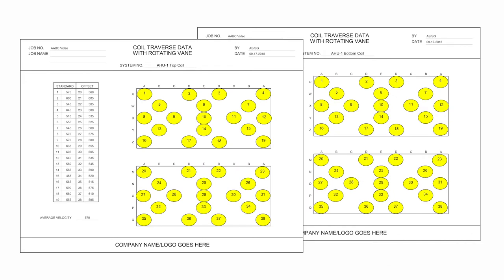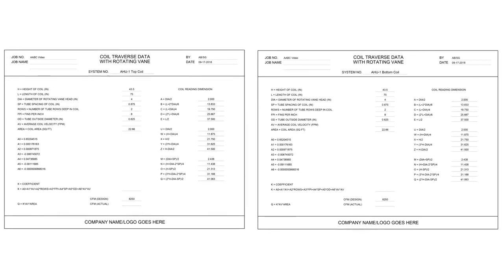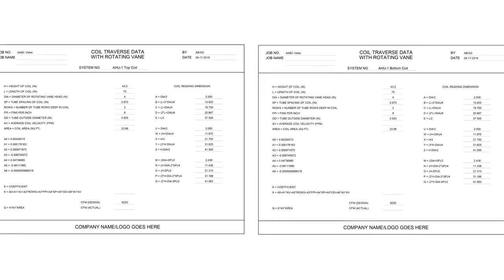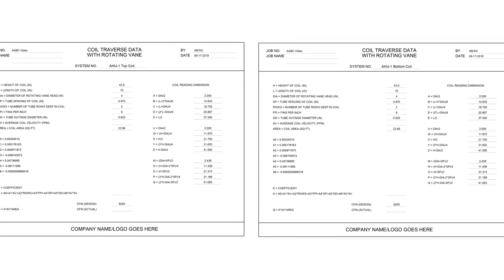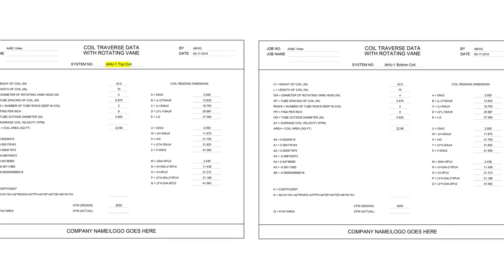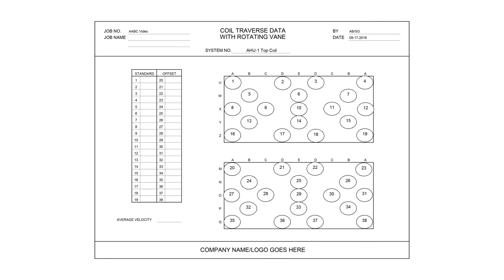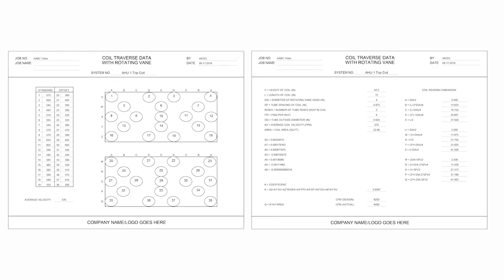The demonstration coil and the AHU-1 Top and Bottom Coils have identical dimensions. The demonstration coil's data from the coil traverse data with rotating vane form was used to input information onto page 1 of the AHU-1 Top Coil and AHU-1 Bottom Coil. On page 2 of the form for AHU-1 Top Coil, record the standard velocity readings. Notice the average velocity at the bottom of the form is automatically calculating. Next, record the offset velocity readings. After all 38 velocity readings are recorded, the average velocity and feet per minute calculation is complete.